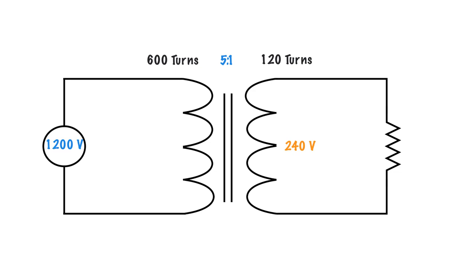Practically, when you're dealing with transformers you won't be given the number of turns. You can still use what's called the turns ratio though because we can still go 1200 volts divided by 240 volts, which gets us our turns ratio of 5 to 1. And that becomes important when we're trying to deal with other calculations such as trying to figure out what the current is.